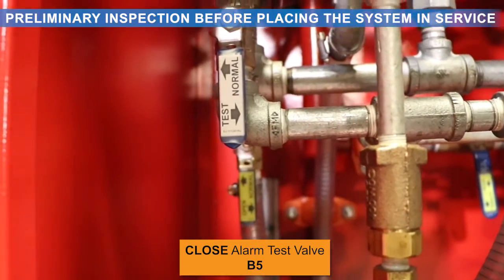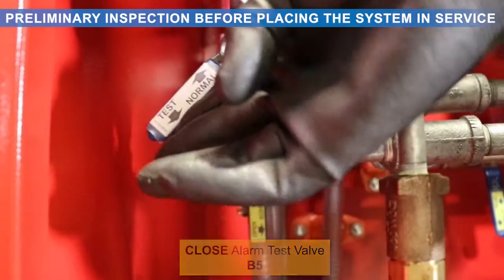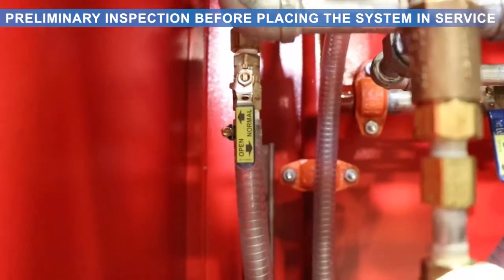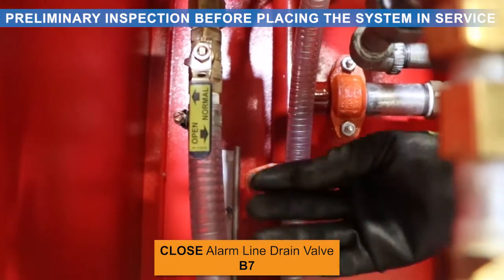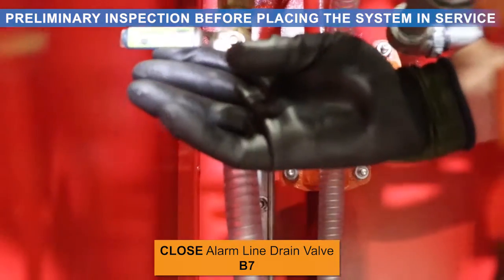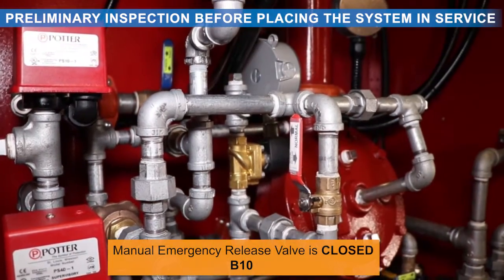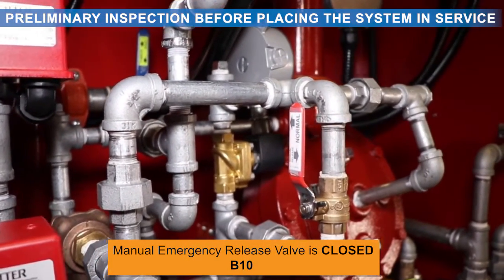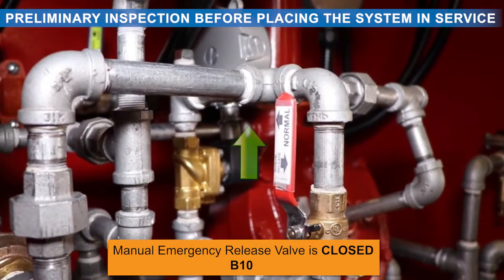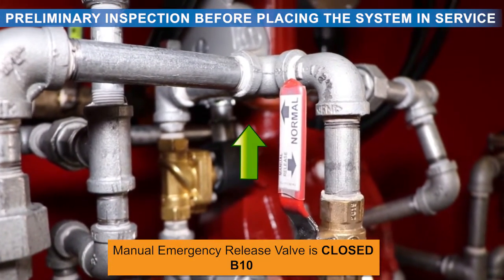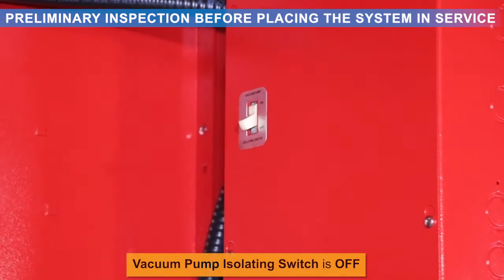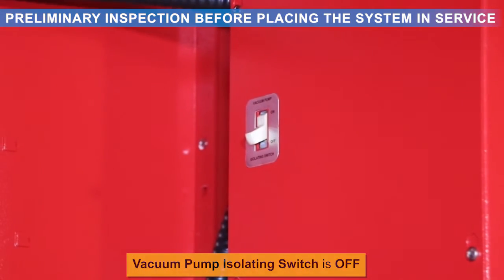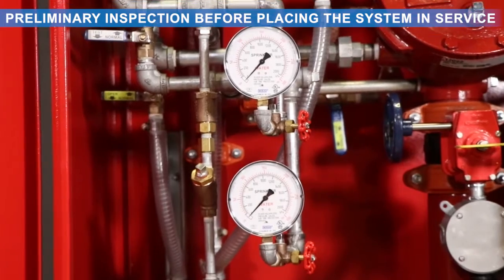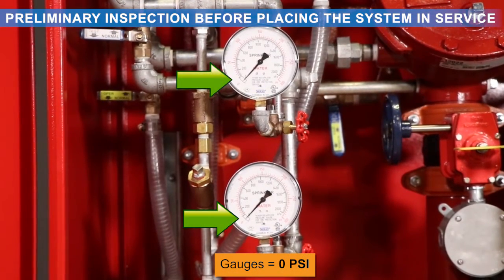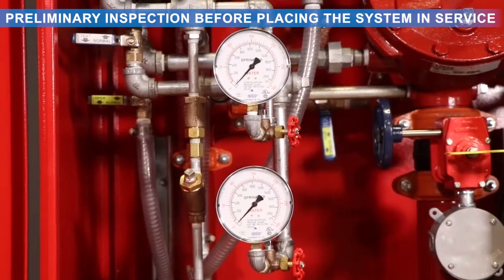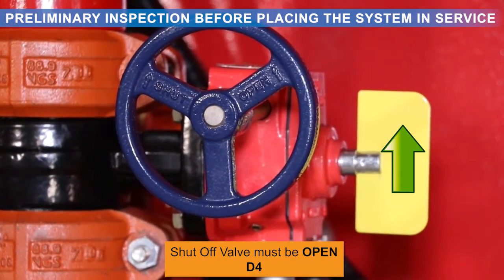Alarm test valve must be closed. An alarm line drain valve must be closed. Manual emergency release valve must be closed. This is a special inverted ball valve that is in closed position when in line with the pipe. Vacuum pump isolating switch must be off. Gauges should show 0 psi. Shutoff valve must be open.